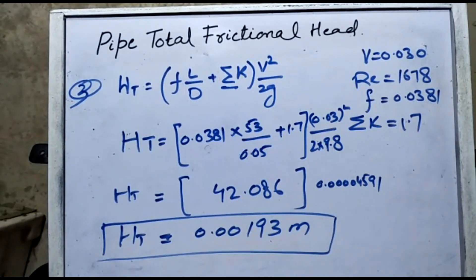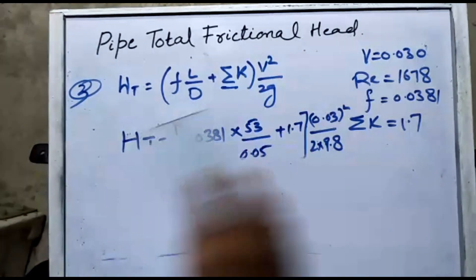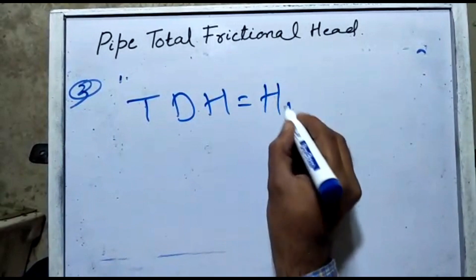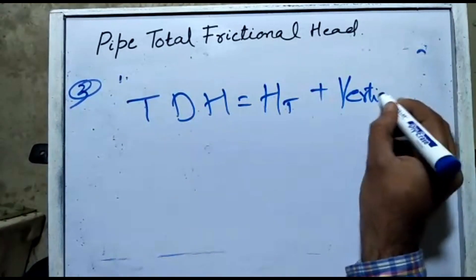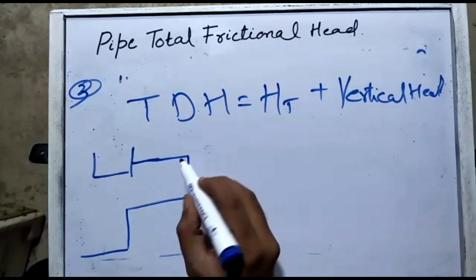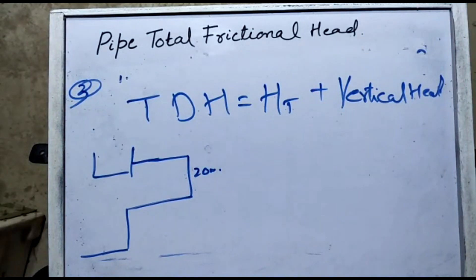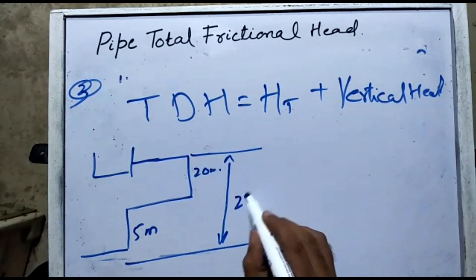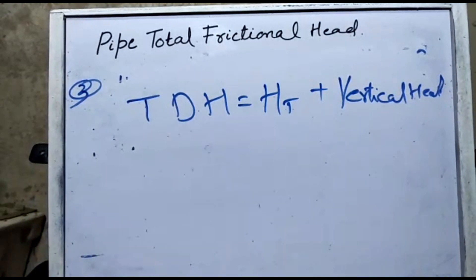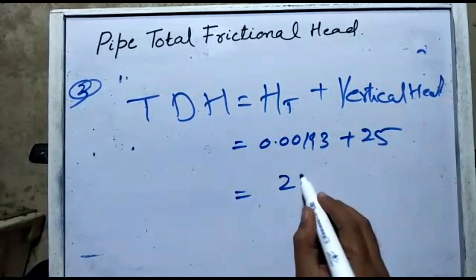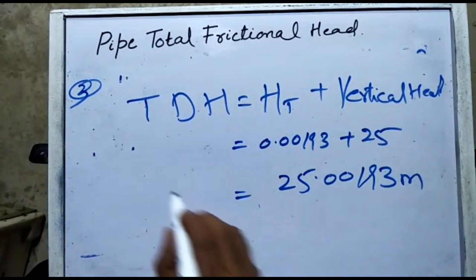The total frictional head from the Darcy-Weisbach equation is 0.00193 m. To find the total dynamic head, we add the frictional head to the vertical head. From the diagram, the vertical height was 20 m + 5 m = 25 m. Therefore, total dynamic head = 25 + 0.00193 ≈ 25.00193 m.